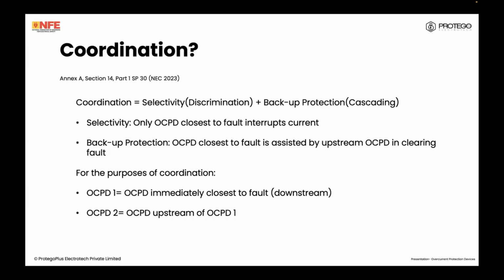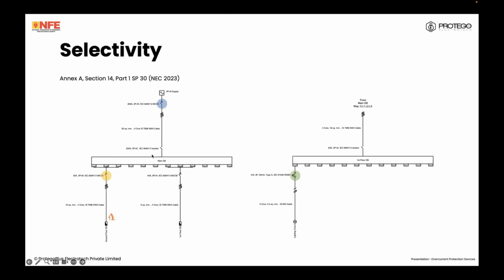We look at some examples. For the purpose of coordination, remember when I refer to OCPD 1, it is the breaker or the OCPD closest to the fault, which is considered as a downstream breaker, and OCPD 2 is the OCPD immediately upstream of this, so let's say supplying this OCPD. So let's look at an example here. I've got my three-phase and neutral supply. I've got an MCCB here. My wires come down here. I've got a main and distribution board. I've got an isolator here. I've got two final circuits, two distribution circuits, sub-main circuits.